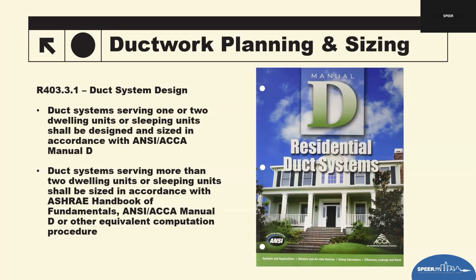So for single family houses and duplexes, the IECC specifically requires duct systems to use ANSI/ACCA Manual D. Manual D takes the heating and cooling loads from the Manual J and the equipment that is selected in the Manual S, and then turns that into a complete duct layout. So that determines duct size based on the actual airflow requirements, the static pressure, the friction loss, the duct material being used, not rules of thumb like all trunks should be 12 inches or all should be 10 inches and then branching off from that. It's basically based on the static pressure being used for design, the friction rates, and then how much airflow is needed to satisfy where it's actually headed.